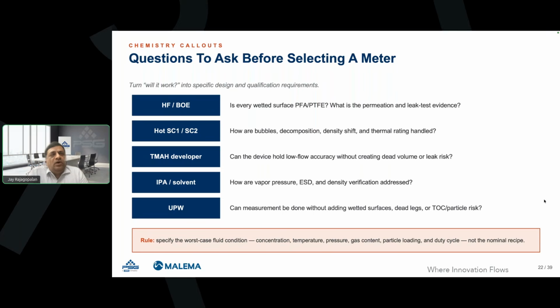Ultra pure water: can the measurement be done without adding any wetted surface? In this case, do I need to really cut the line, because the ultra pure water is already extremely pure, and do I need to add a device which can potentially contaminate? So the clamp-on could be a choice there, as we mentioned.